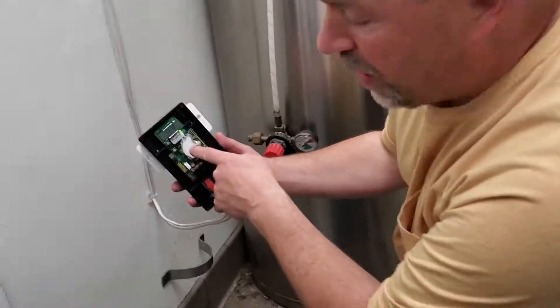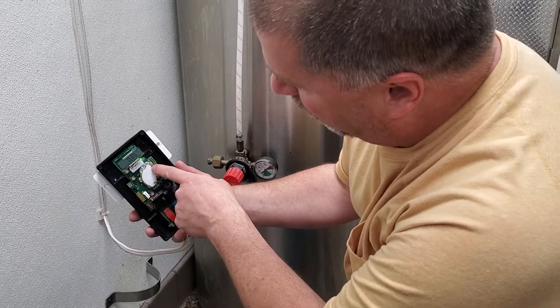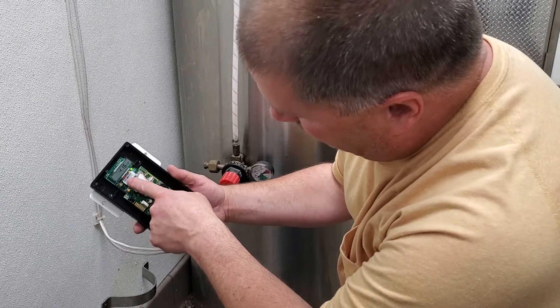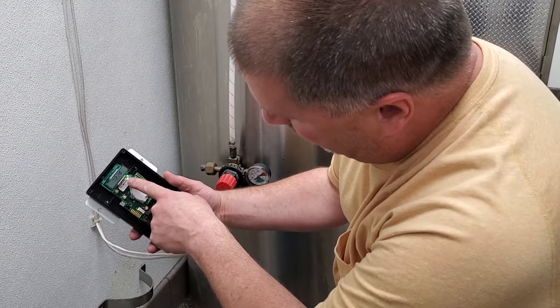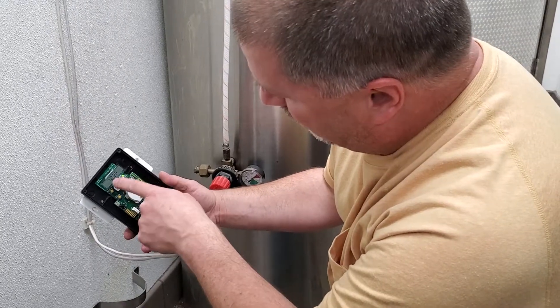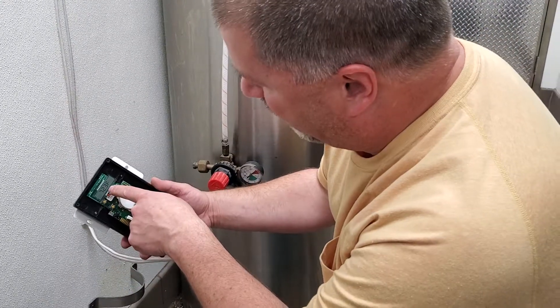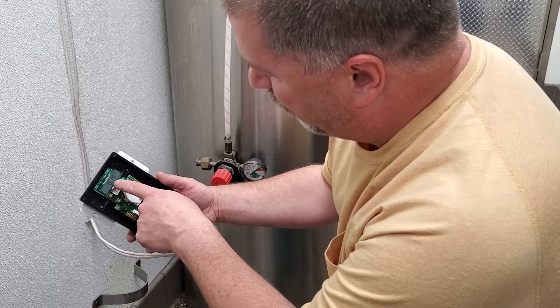So that's the CO sensor, and it does blink a yellow light there, but I think that's just normal. This is the yellow light for the air up here, and it's not lit. So that's normal — the alarm light is not lit. It's 0.26% CO right now because I have been doing it. I tested it twice already. Normally it's like 0.03%.